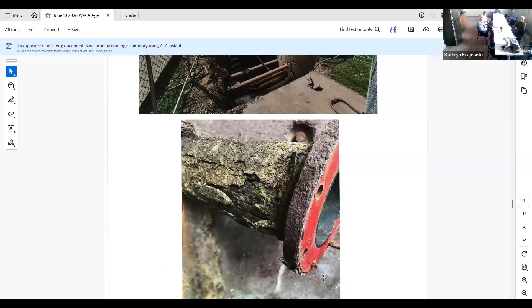So we have a lot of equipment here, we started digging in the wet well. There's 3 pumps, 375 horsepower each, and 3 discharge lines. The one on top on the left in orange is your pressure line. There's a regulator on top so that if you get a surge of pressure in your force main, that 6-inch line acts as your pressure relief.